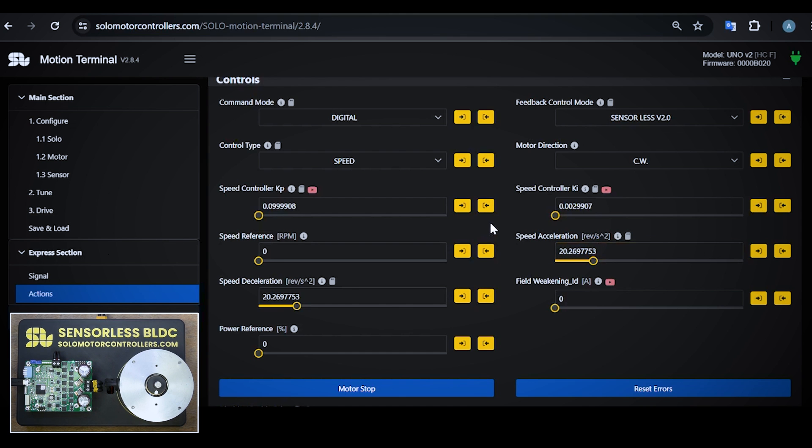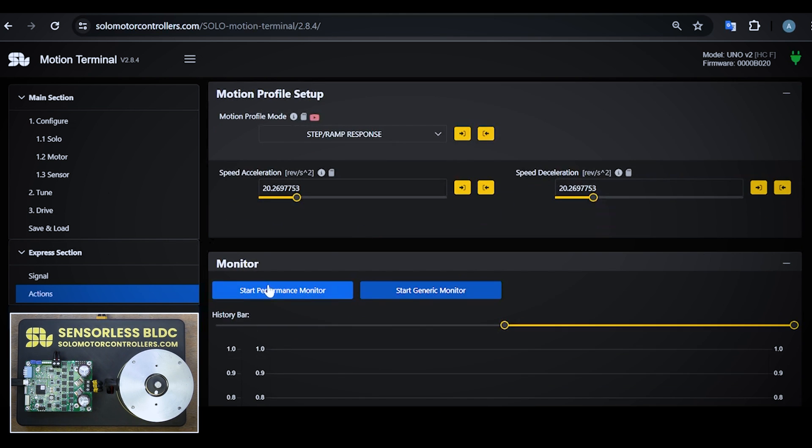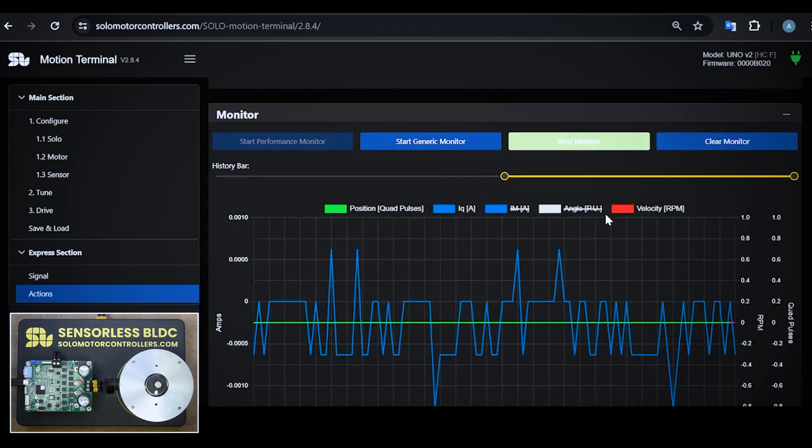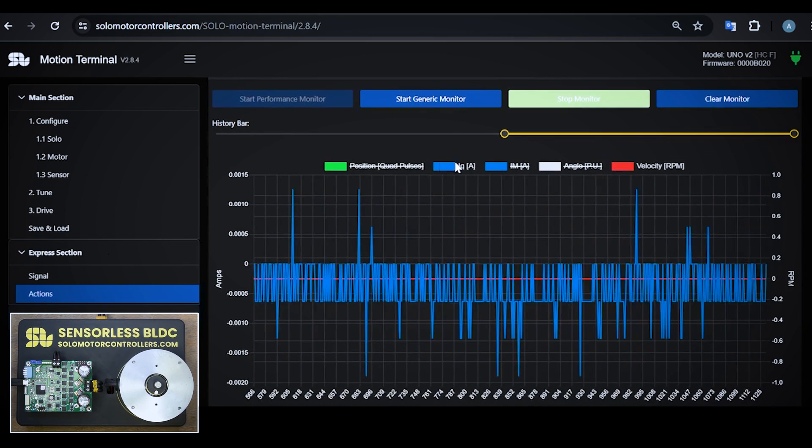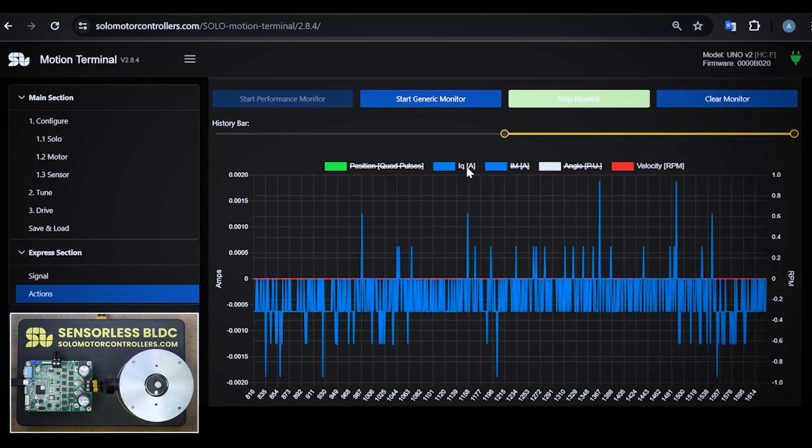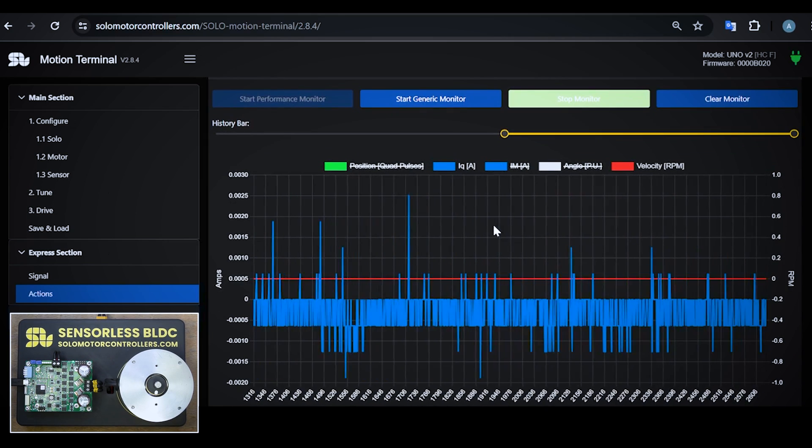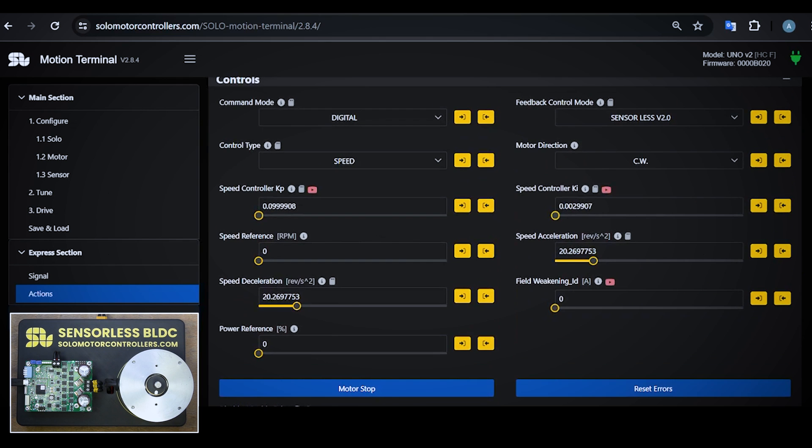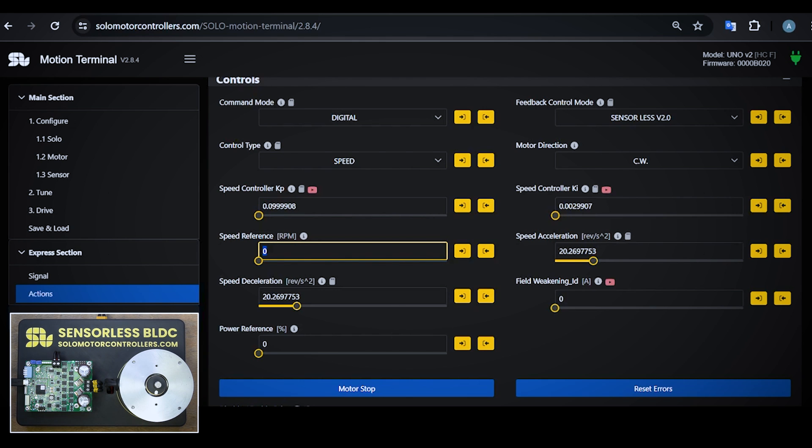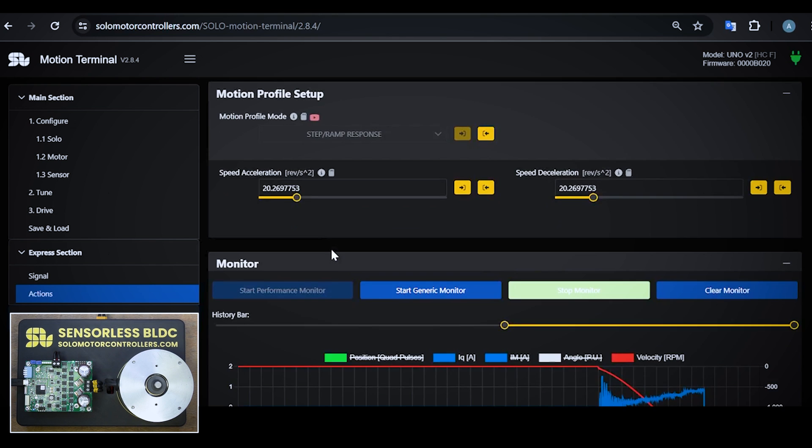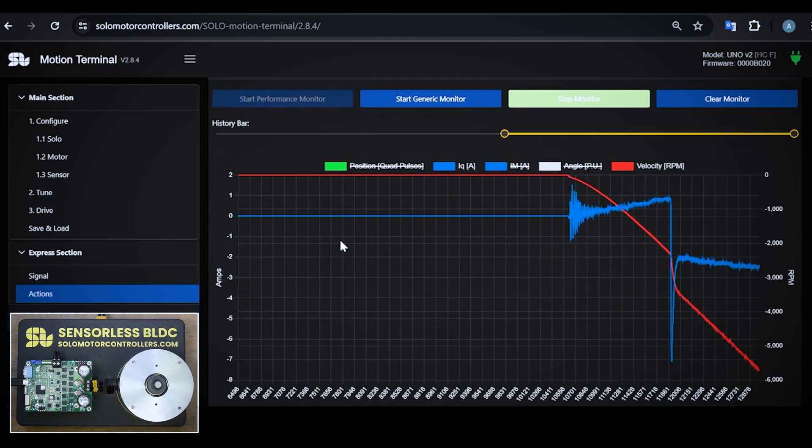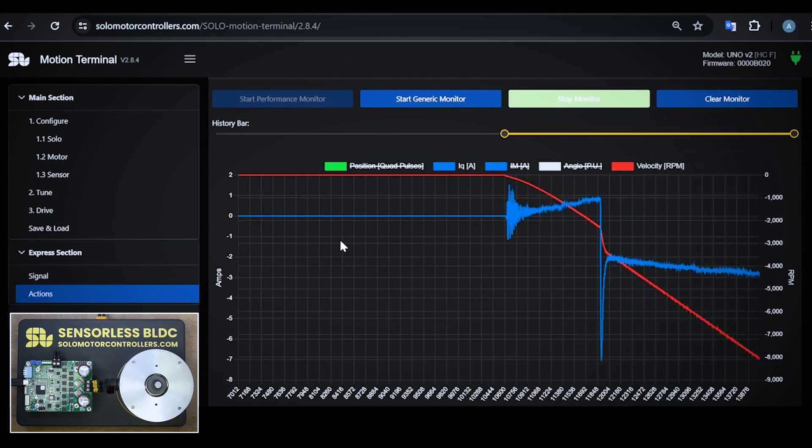Anyways, 20 revolution per square second is a good number. So what I'm going to do is this: I'm going to run the performance monitoring and have an eye on the IQ, which is the torque of the motor, and the speed. The goal I have here is, after setting all these parameters, reaching to the nominal speed of this motor which is 16,000 rpm, and then go up and down and see what happens. So let's start with 10,000 rpm.